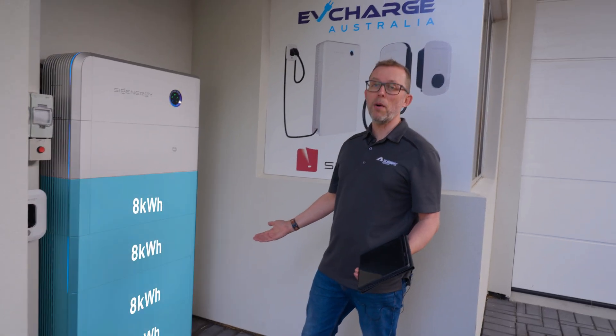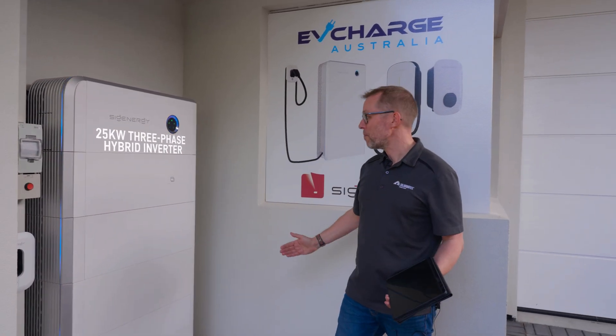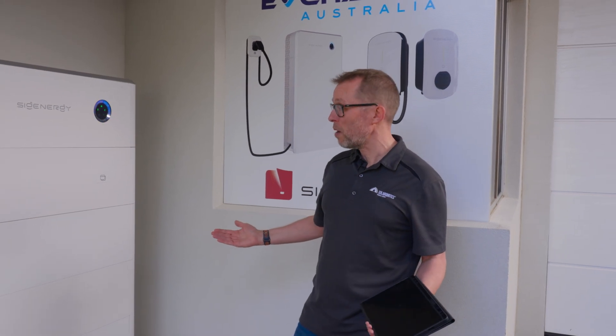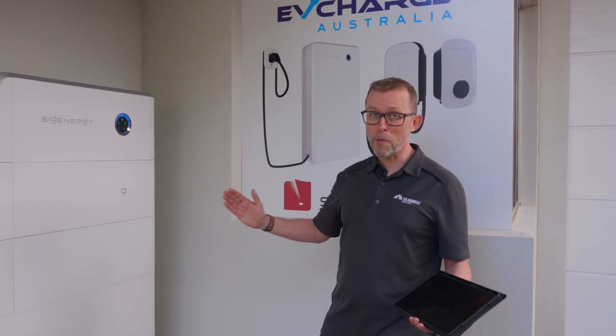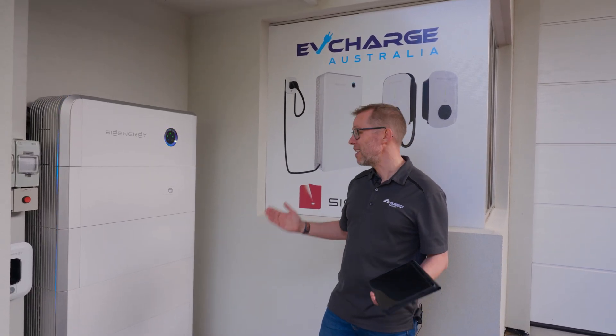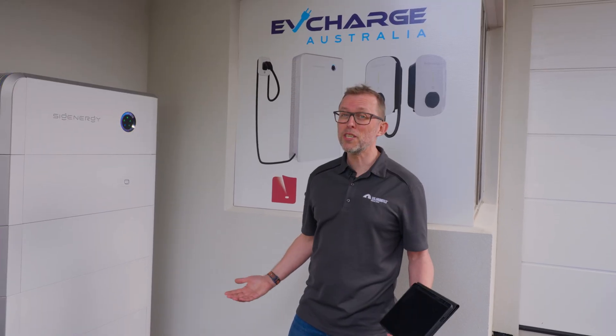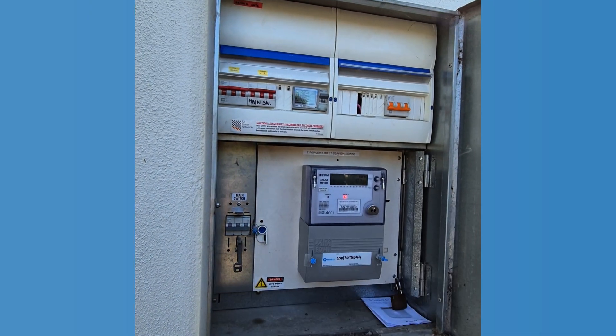Let's go through what we've got: four 8 kilowatt hour battery modules — 32 kilowatt hours of storage — an EV DC charger, and a 25 kilowatt solar inverter. That's about $28,000 Australian dollars just in hardware, plus installation. But what you're getting is 32 kilowatt hours of storage, a 25 kilowatt DC fast charger, a 25 kilowatt three-phase solar inverter with full three-phase house backup, and it's bi-directional ready with just a simple software update — no hardware or wiring changes. We're waiting for compatible cars, which are about six to twelve months away, and for local electricity networks to give permission to operate bi-directionally on the grid. What I'm pretty sure is Australia's fastest home EV charger, here in little old Adelaide.